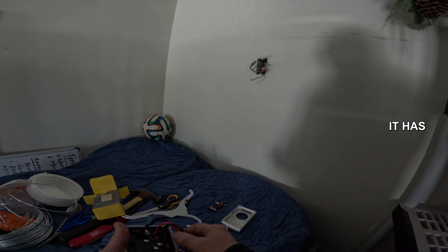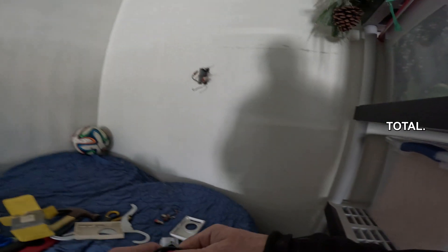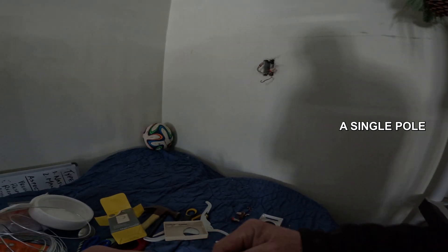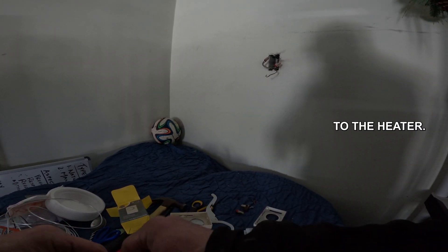I just went and bought a two-pole, which is significant that it's a two-pole. That means it has two sets of wires, four wires total. If it just had one set of wires it would be a single pole and it wouldn't shut power off completely to the heater.